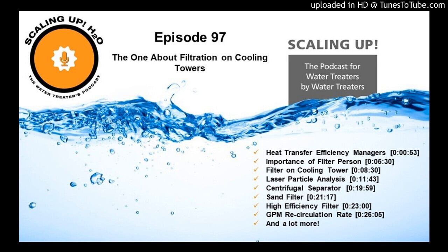But it's good to go and look at the pump at the cooling tower and see what the GPM rating on the pump is. And then the question is, if you've got several cooling towers, how often do they all run? What is the high load time? During the warmer months of the year, what's the percentage load on the cooling tower? Because that will tell you what the amount of bleed rate coming out of the cooling tower is in order to maintain particular cycles that the water treater's got it set at.